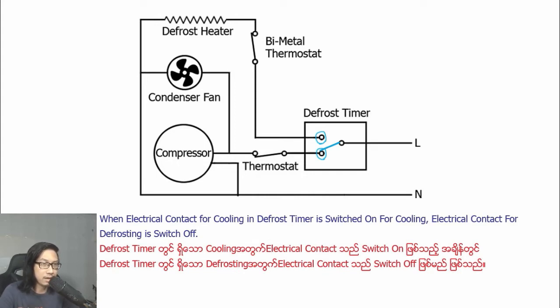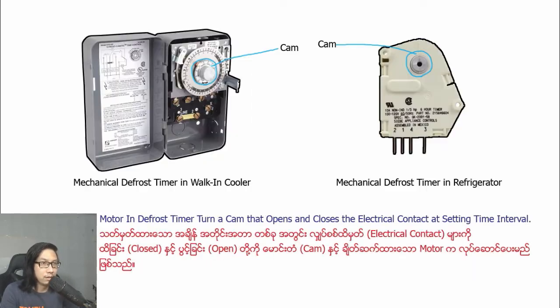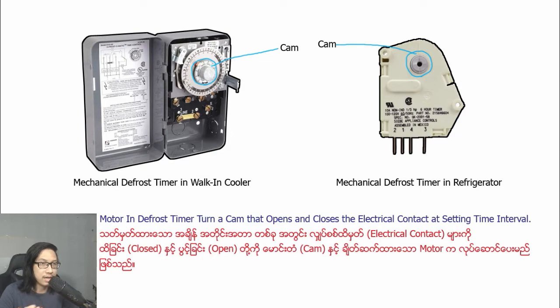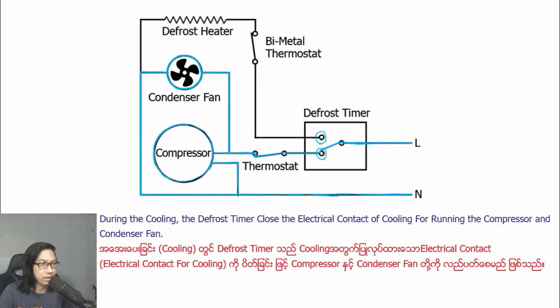When the electrical contact for cooling in the defrost timer is switched on for cooling, the electrical contact for defrosting is switched off. The motor in the defrost timer opens and closes the electrical contacts at certain time intervals. During cooling, the defrost timer closes the electrical contact for cooling, running the compressor and condenser fan.